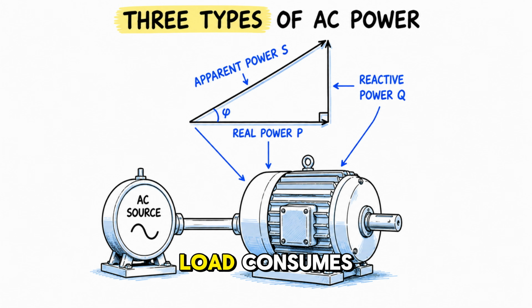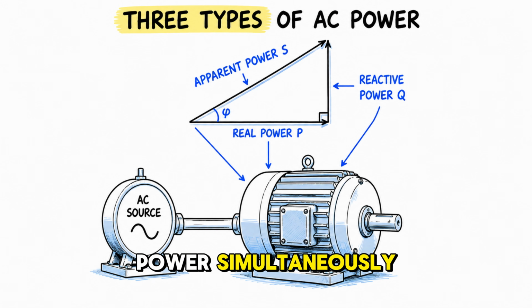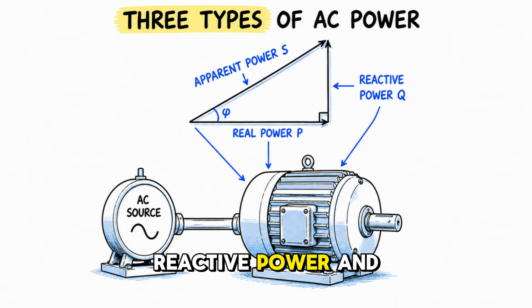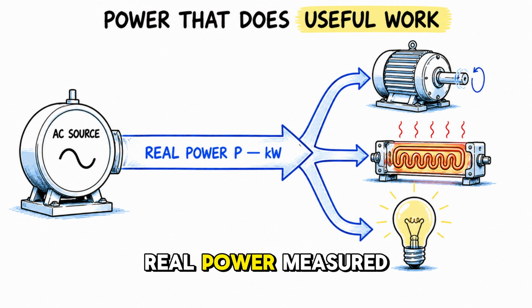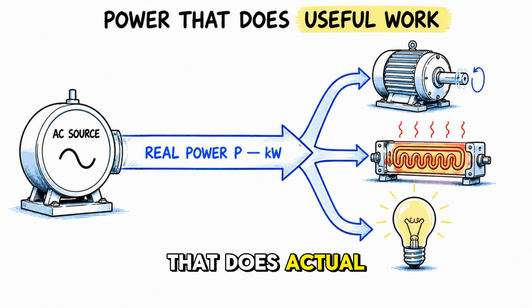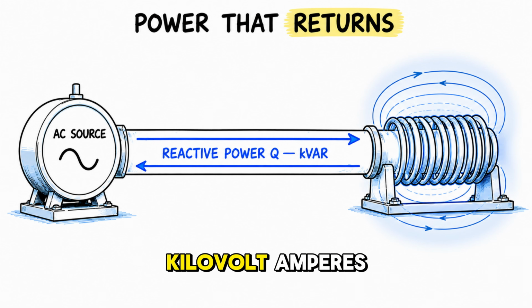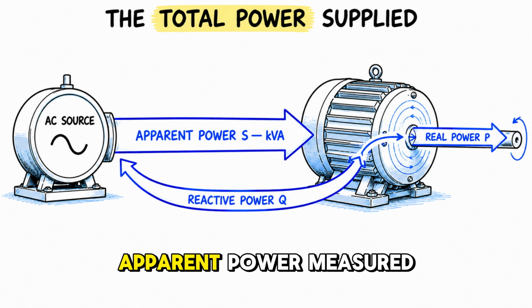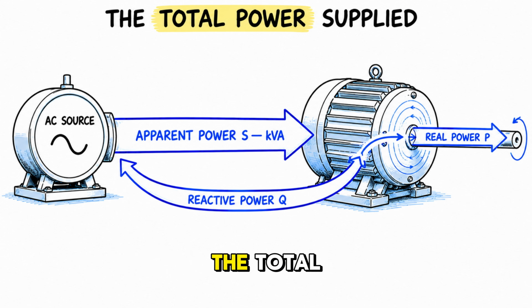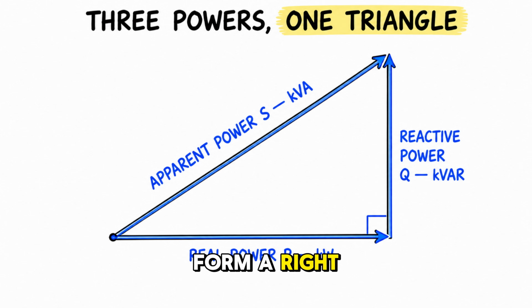Every AC electrical load consumes 3 types of power simultaneously: real power, reactive power, and apparent power. Real power measured in kilowatts is the power that does actual useful work. It runs motors, produces heat, and generates light. Reactive power measured in kilovolt amperes reactive is the power that bounces back and forth between the source and the inductive load, doing no net work. Apparent power measured in kilovolt amperes is the total power the supply must provide to deliver both real and reactive power to the load. These 3 quantities form a right-angle triangle.